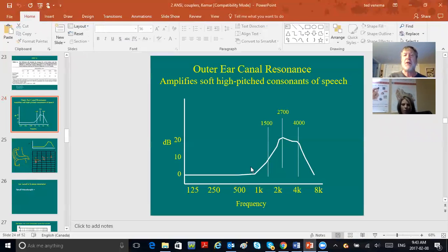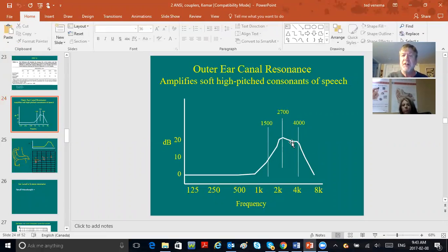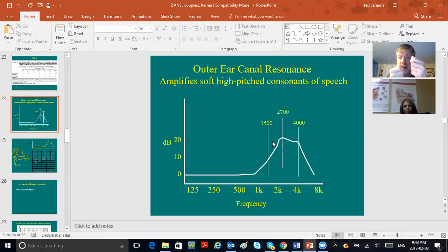Today we no longer even do that in real ear. We don't really care about the unaided response of the ear much anymore—it's mainly used to tell whether the tube is close enough to the eardrum. If it's not close enough, the response at 4000 Hz will drop off. So we use the outer ear canal resonance as a visual guide to help decide whether the tube is close enough, though you can also look with an otoscope.